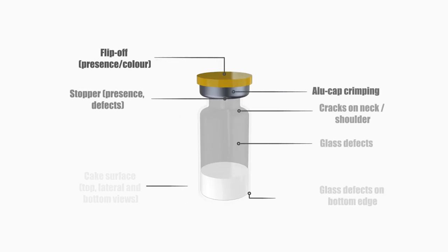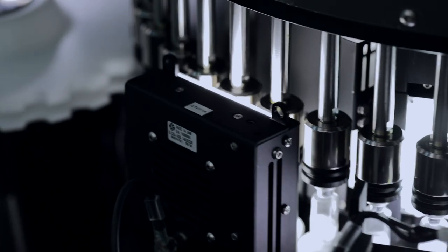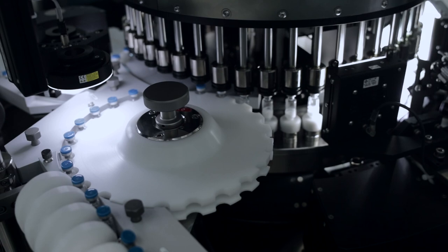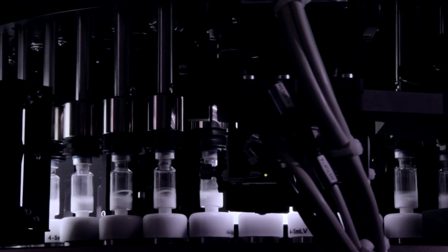Cake inspection is performed from different angles, covering the complete product surface using high-resolution cameras. The acquisition of a considerable number of frames is the key to ensuring accurate detection and low risk of false rejects. The application of structured light systems combined with electronically adjustable light intensity, verifiable during each image acquisition, efficiently complete Brevetti C.E.A inspection technology.